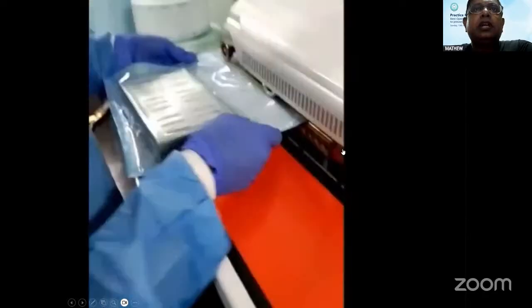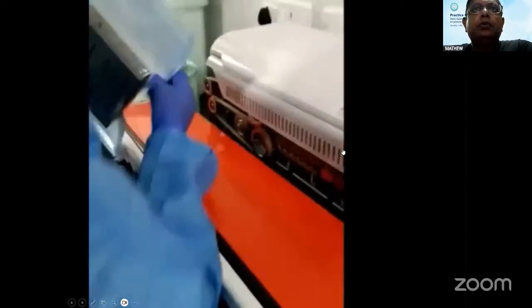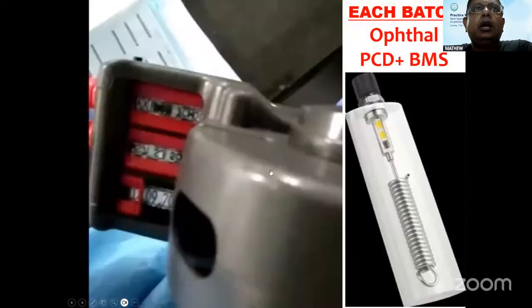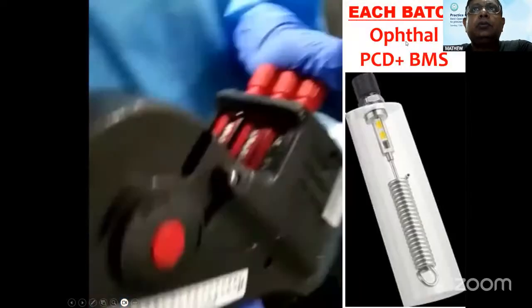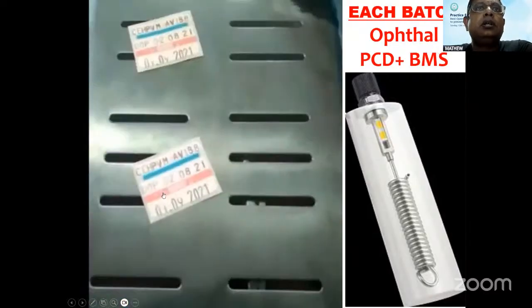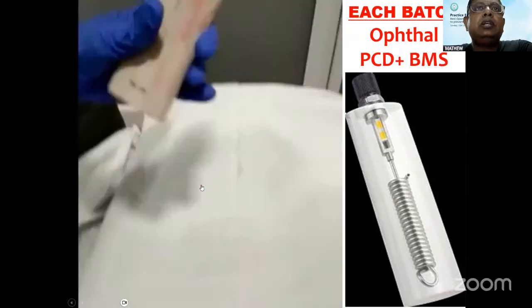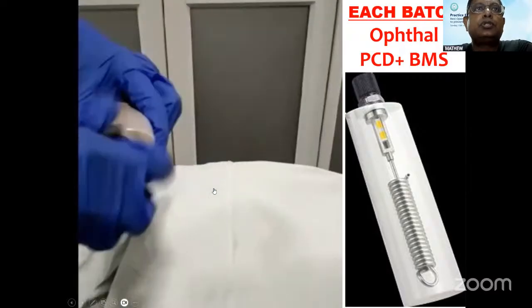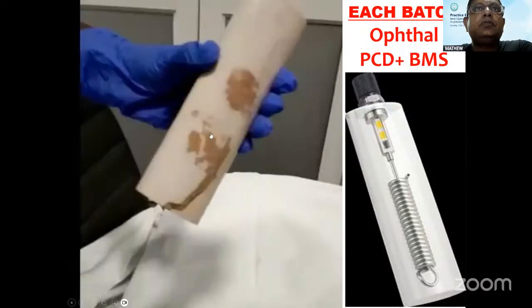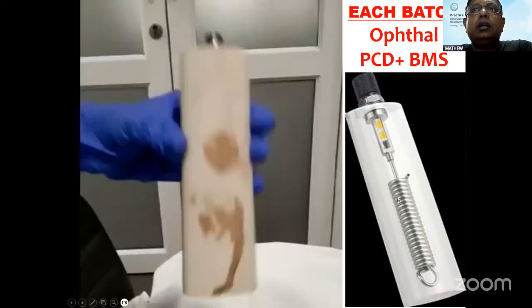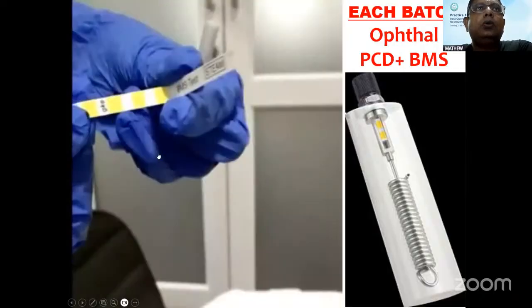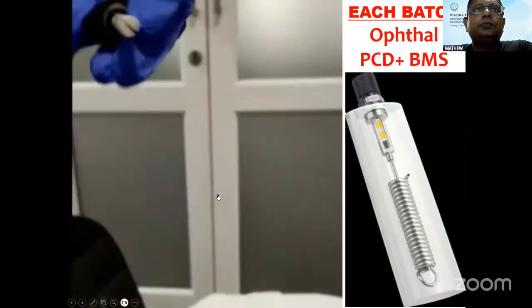This is a typical pack that we use. That is a cataract set. One single pack is adequate if it is used the same day. Double packing can be used. And along with that, for each batch, we have the Ophthal process challenge device with a batch monitoring strip. That is the monitoring strip, blue in color when it is not exposed, black after it has been exposed. And this is the process challenge device, which is the Ophthal PCD. And this is a cross section, yellow when it is not exposed.